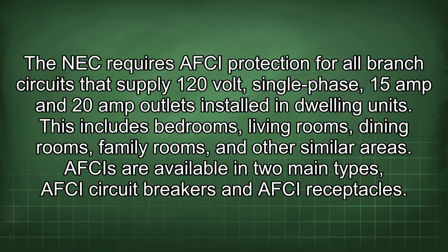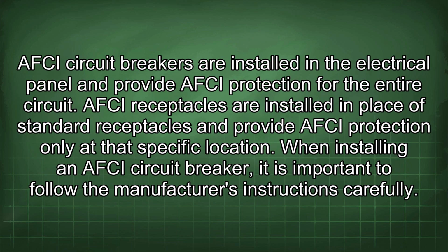The NEC requires AFCI protection for all branch circuits that supply 120-volt, single-phase, 15-amp and 20-amp outlets installed in dwelling units. This includes bedrooms, living rooms, dining rooms, family rooms, and other similar areas. AFCIs are available in two main types, AFCI circuit breakers and AFCI receptacles. AFCI circuit breakers are installed in the electrical panel and provide AFCI protection for the entire circuit. AFCI receptacles are installed in place of standard receptacles and provide AFCI protection only at that specific location.